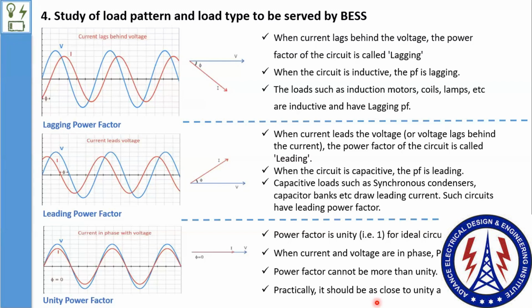At the point of connection with the grid, your voltage reaches first and then the current follows, creating unwanted harmonics at their end. The grid operator doesn't want this disturbance, as it can make the grid unstable because of your plant, and they don't want their operations disturbed by anyone.